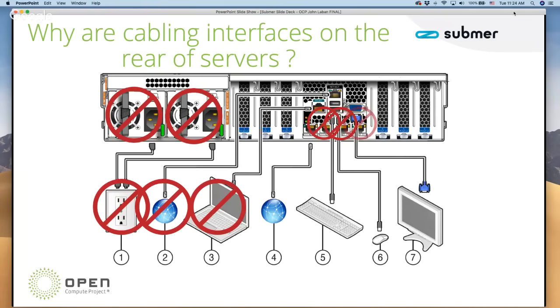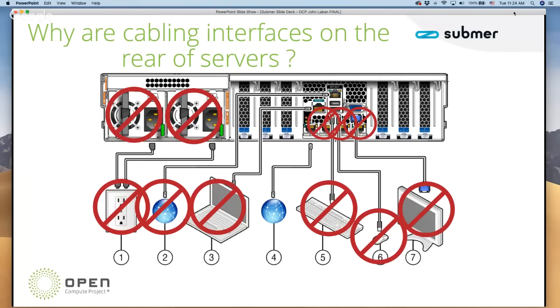Multiple operational Ethernet ports become unnecessary when you use virtualization with lightweight containers; you can get away with just 1 or 2. So on an OCP server, you've got 1 or 2 Ethernet ports on the front, because when you plug the server into the rack, it just clicks onto a DC bus bar. It's very, very simple.